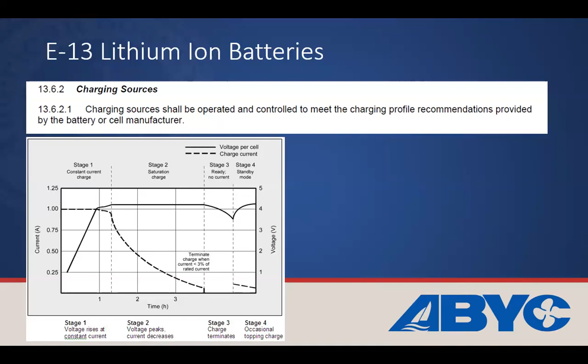Installation, some key installations. Again, the requirements are to follow the manufacturer's requirements for installation. If they are not provided, there shall be no visible movement of the battery. So this is different than what we require of a lead acid battery. For a lead acid, we allow up to 1 inch of movement. Here, we basically say that they should not have any visible movement, so they should be securely held in place.